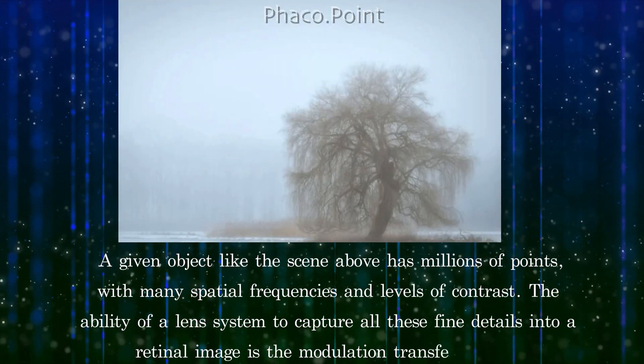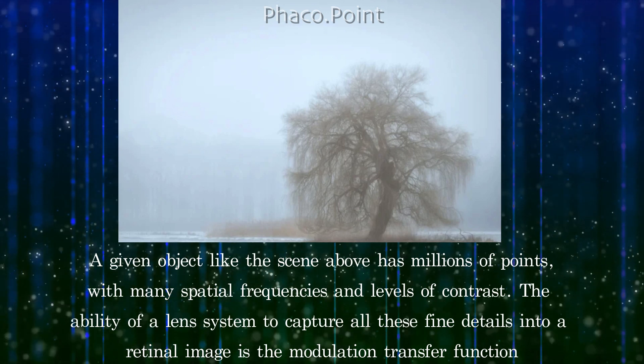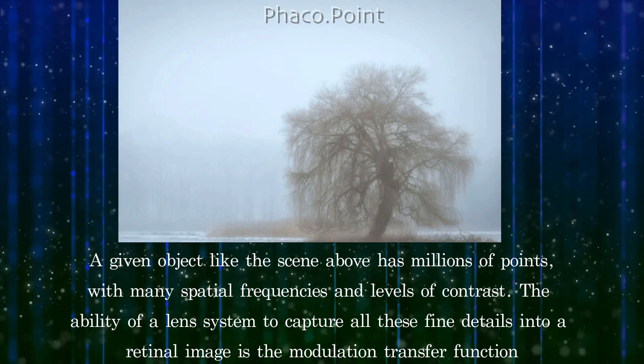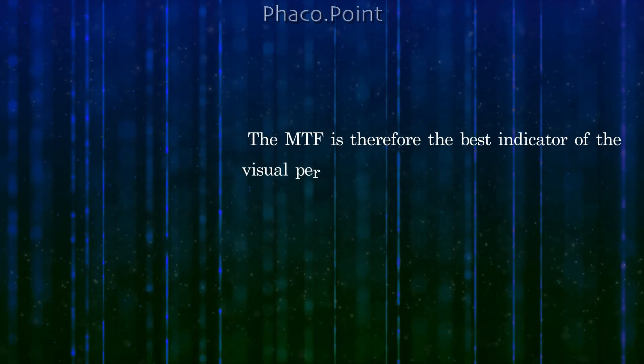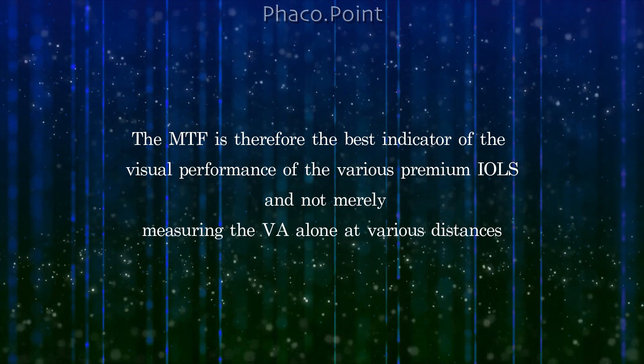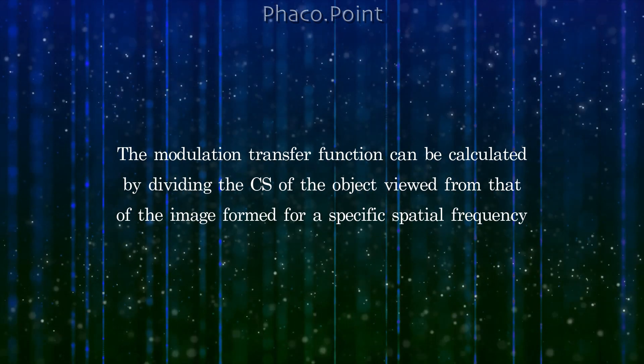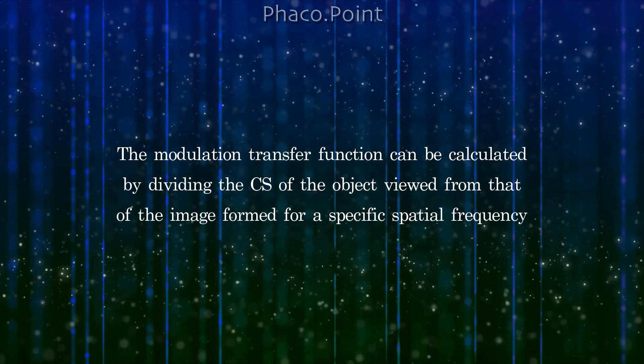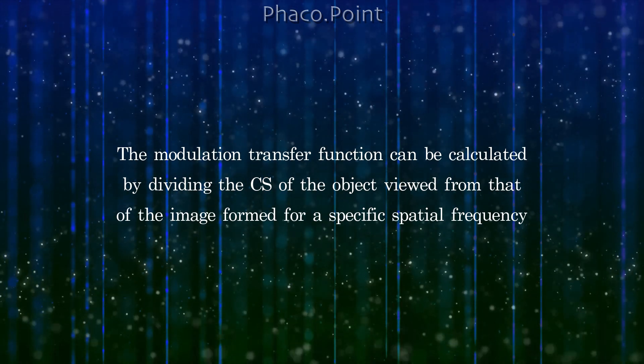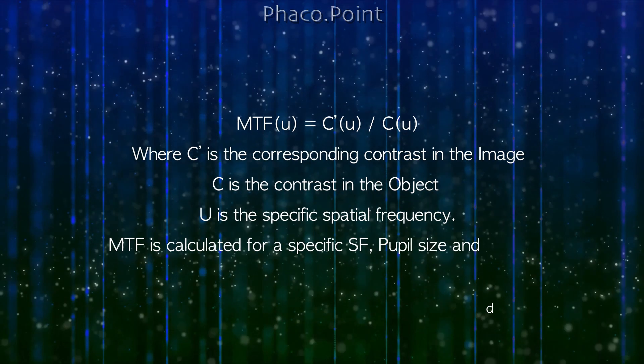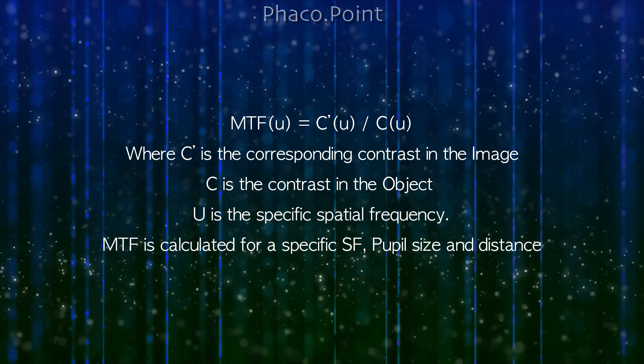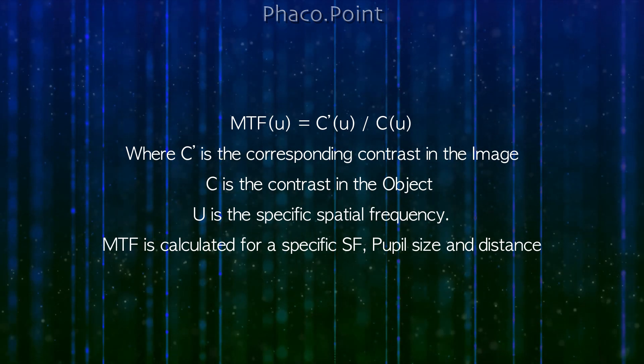A given object has millions of points with many spatial frequencies and levels of contrast. The ability of the lens system to capture all these fine details into the retinal image is called the modulation transfer function, and hence it depicts visual quality. The MTF is therefore the best indicator of the visual performance of premium IOLs, and not merely measuring visual acuity at various distances. The modulation transfer function is calculated by dividing the contrast sensitivity of points in the object viewed by that of the contrast sensitivity in the image formed for a specific spatial frequency. MTF is calculated for a specific spatial frequency, pupil size, and distance.